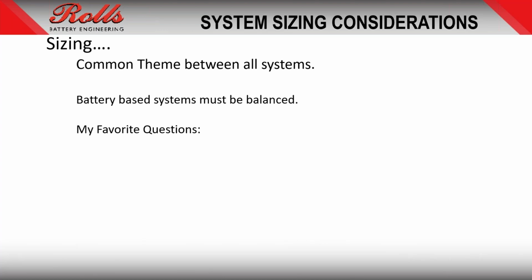The number one reason I do is I don't sell full systems anymore. But if you sell full systems and you're doing the installation, it's a good idea to charge for the energy audit. You drive out there, you put some meters on, you check where the surge loads are, you check what the actual loads are, you leave the meter for a few weeks or a few days to ensure how much load the client's actually pulling, and then you can figure out what size system they can get, what size system they need.